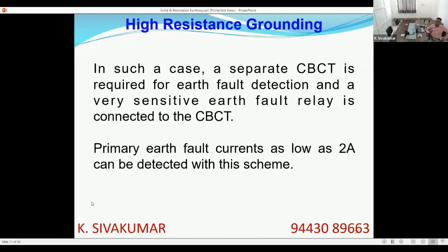unbalances during switching on of a transformer, during switching on of motors, cables. Some zero sequence element may be present during switching on. At that time, they should not trip. So there must be a time delay also inbuilt in such a protection.